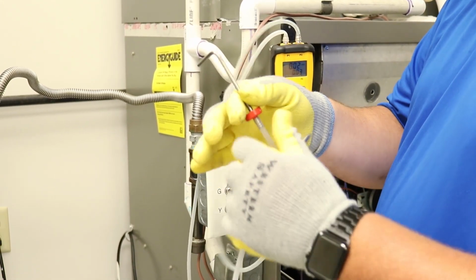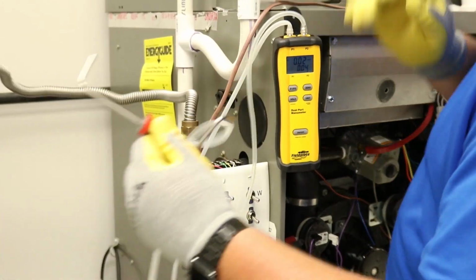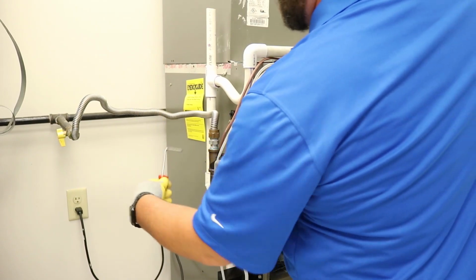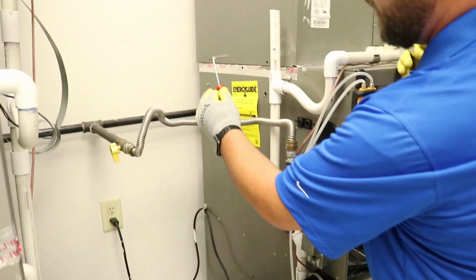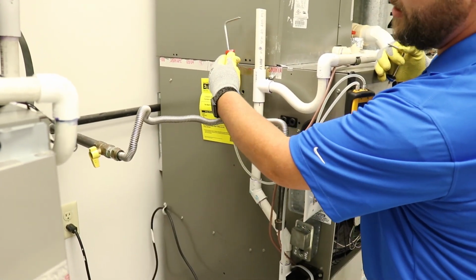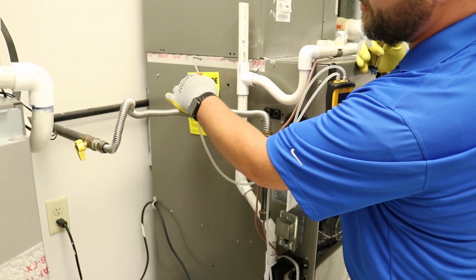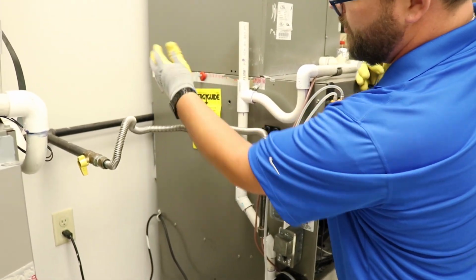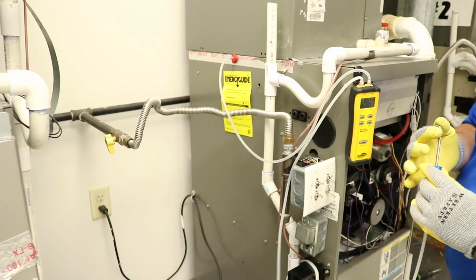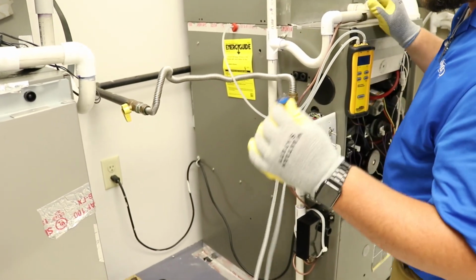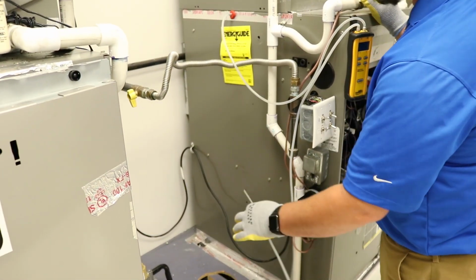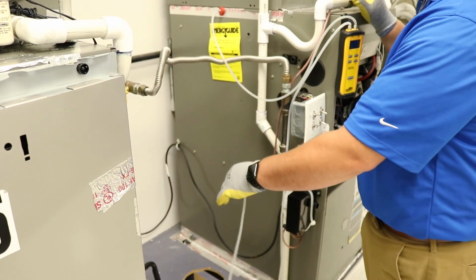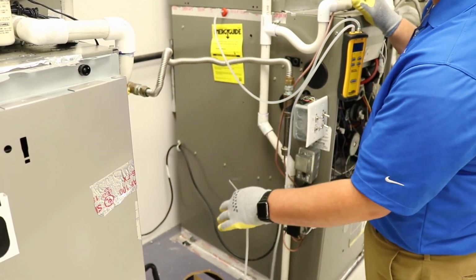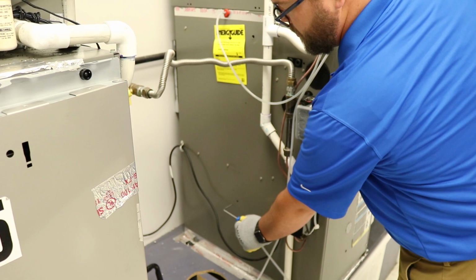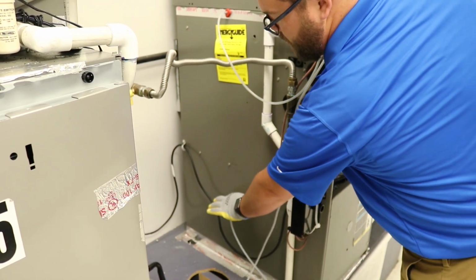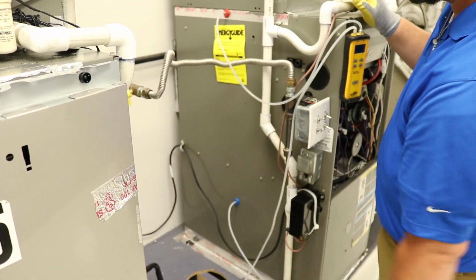So let's start with our first probe here. We're going to reach around the furnace and insert it. As you can see, this is the evaporator coil. We're going to insert it in a hole that's still within the furnace. That's static probe number one. Our second one is going to be on the other side of the heat exchanger, but still inside this box. Remember, keep it inside the box. So for this one, it's going right next to the blower motor, and they're both in place.